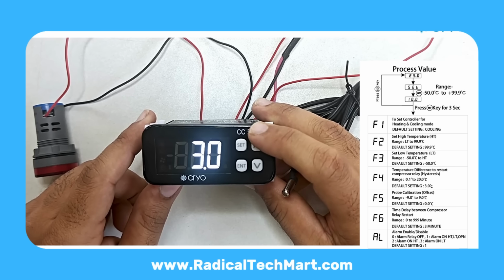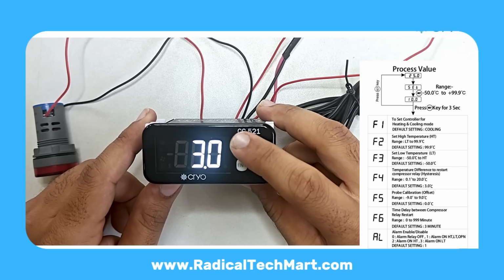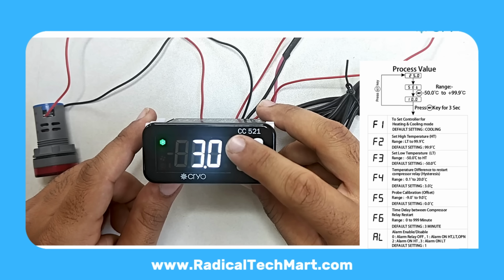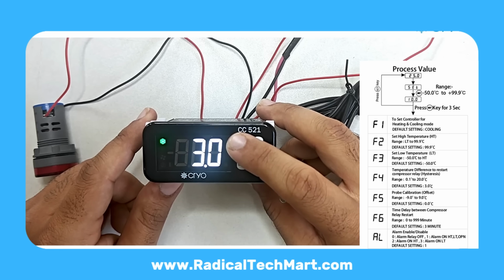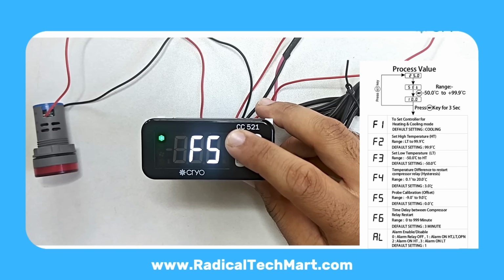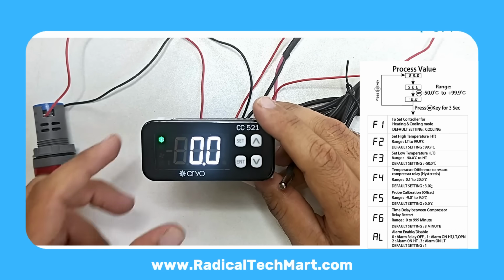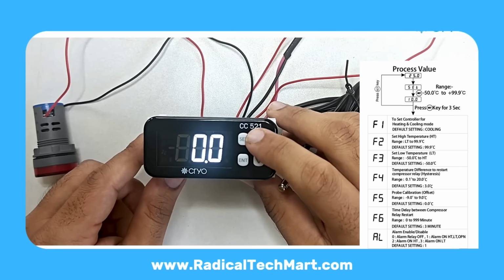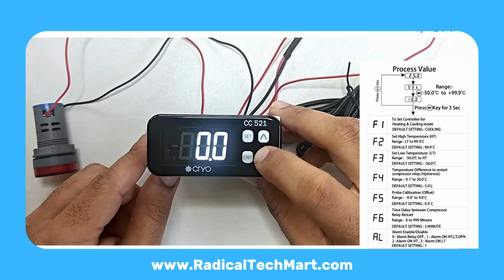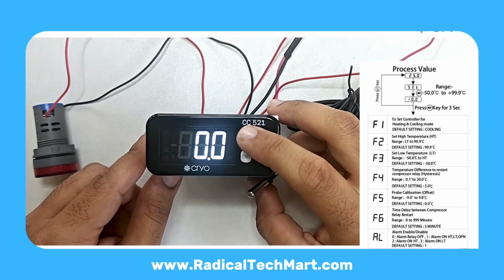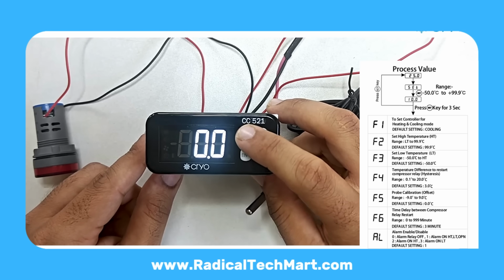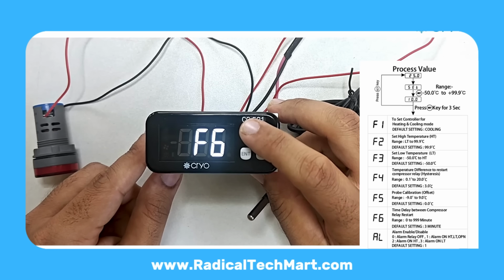Example, if your set point is 30 degrees Celsius and tolerance is equal to 3 degrees Celsius, the compressor turns on at 33 degrees Celsius. It turns off once the temperature drops back to 30 degrees Celsius. F5 Offset Calibration. If you want to shift the reading, for example, +1 degree Celsius or -1 degree Celsius, enter the offset value here. F6 Compressor Delay Time.